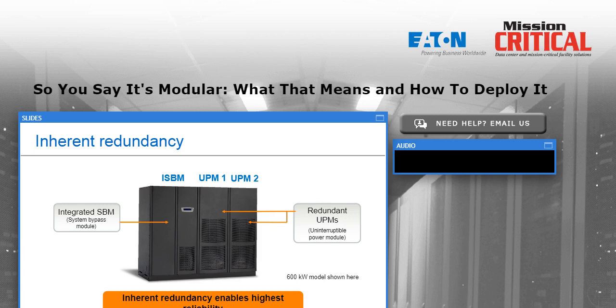It can continue to operate and provide conditioned power and battery backup until, for example, a service person arrives to work on UPM2. So that gives me the benefit of a multi-module, discrete, parallel redundant UPS system without having to incur the upfront cost and footprint of a multi-module system that would require two separate UPSs, each with large amounts of battery backup and switchgear to connect the two together in parallel. So this capability allows that inherent redundancy in a single box UPS system.